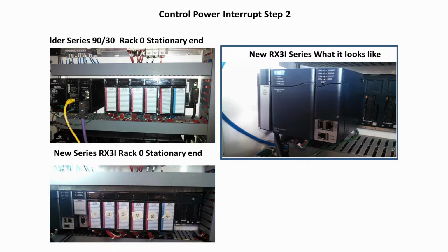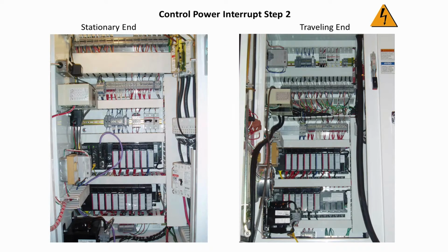In the 9030 portion of the video, there are 6 quick checks to use to discover the cause of the power interrupt error message in Step 2. In the RX3i portion of the video, quick checks number 2 and 3 are different, but quick checks 1, 4, 5, and 6 are the same for both the RX3i and the 9030. So be sure to view the entire video. After completing Step 1, we know we do not have 120 volts on wires labeled 2S or 2T, which means that either CR1 or CR2 is not engaged. Follow these quick checks to locate the problem.